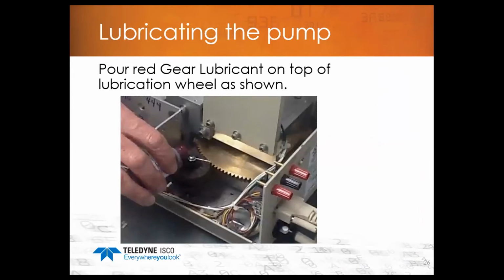And there's the, it's kind of a felt pad, and that's the lubrication wheel. And that lubrication wheel is what you'll use the red aerosol lubricant on. And you just want to put a fairly good amount on that soak pad, because that soak pad is always in contact with the brass worm gear when the pump is running. And so just soak it pretty good, and that's really all you have to do. And then that soak pad will constantly keep your worm gear and also the horizontal worm, which you can't see in this photo, constantly lubricated.